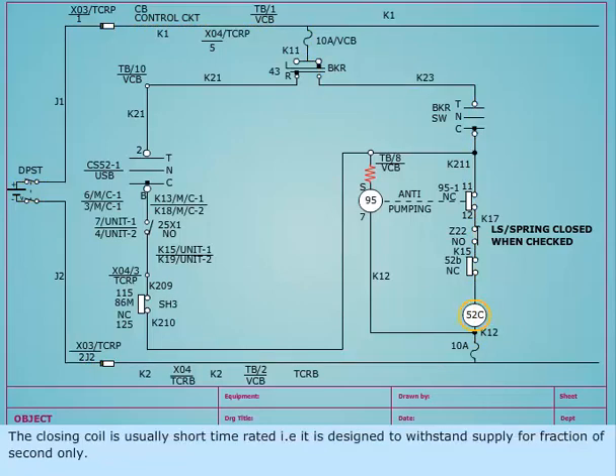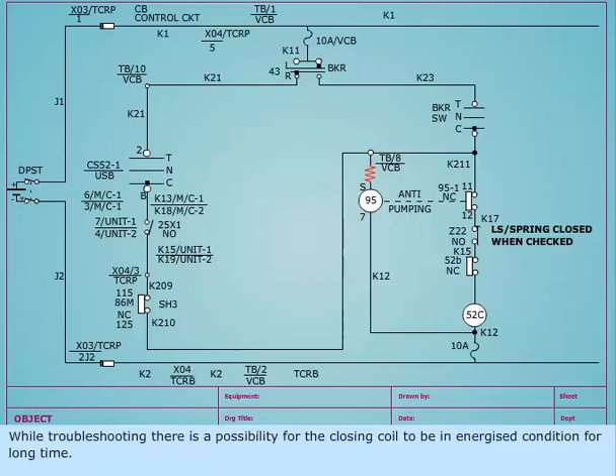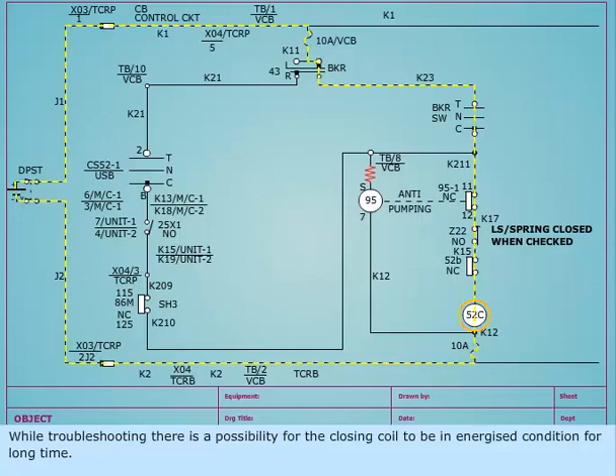The closing coil is usually short time rated, meaning it is designed to withstand supply for a fraction of a second only. While troubleshooting, there is a possibility for the closing coil to be in an energized condition for a long time.